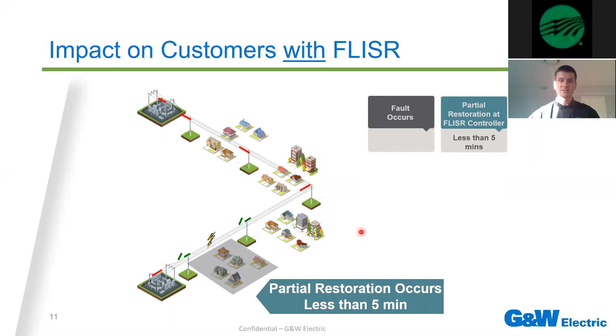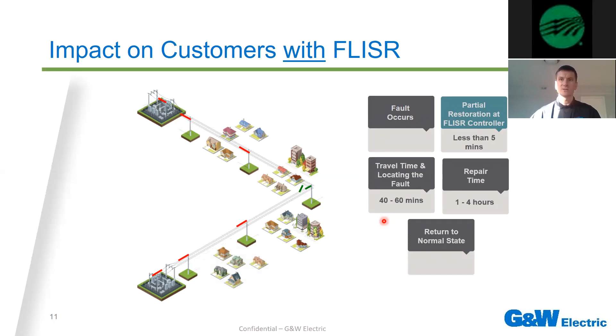Still, for a crew to be notified and say, hey, the automation system operated, or customers still calling in and saying, hey, we are affected by a fault, that's around the same time. The repair time also doesn't change. But what's important is that this first initial partial restoration, meaning that you supply customers not affected by the fault with power as quickly as possible, happens in a matter of minutes and no longer in a matter of hours.